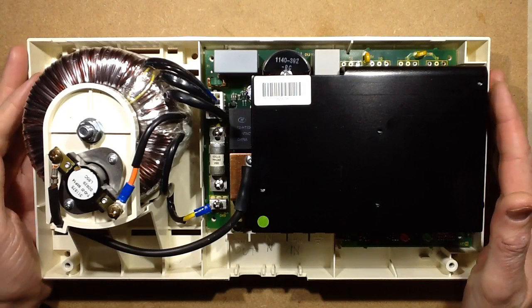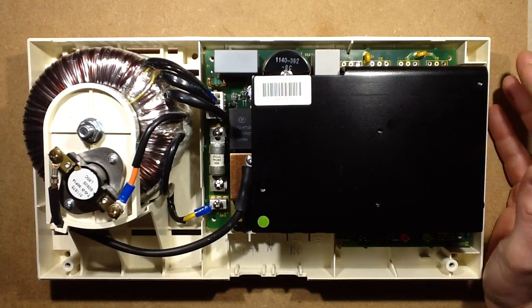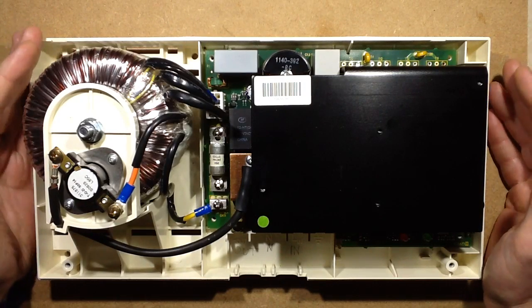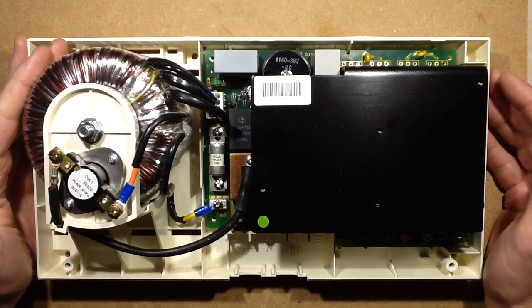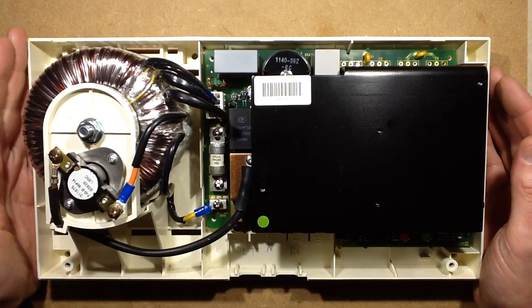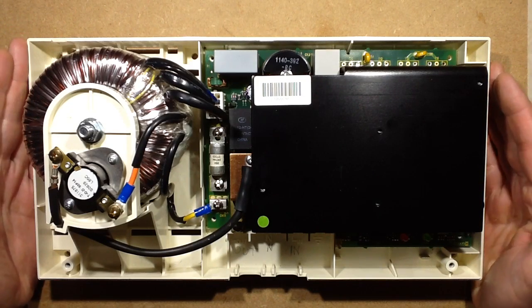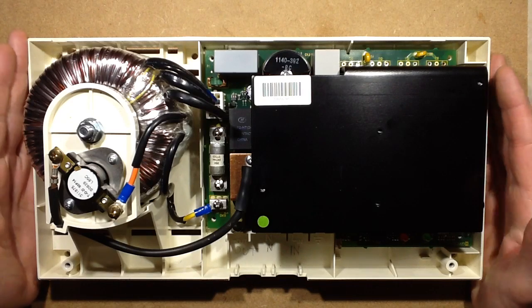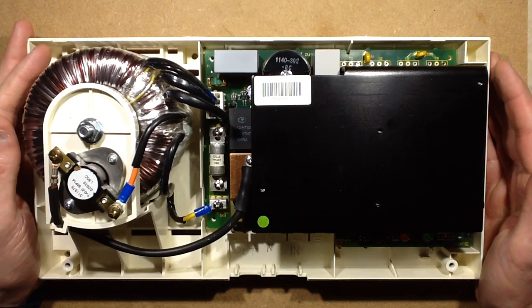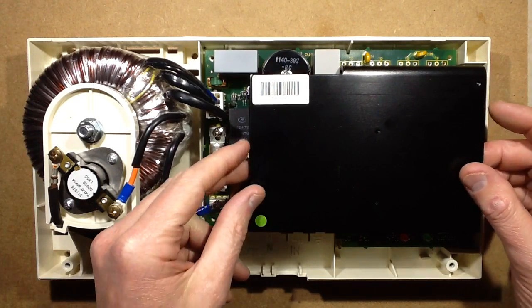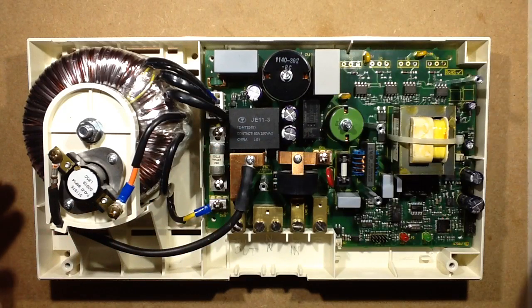This is a rather interesting unit. It was sent to me to do a sort of autopsy on as to why it had failed, because it was blowing fuses all the time. It's a V-Phase VX1 energy saving device, and it basically goes in at your distribution board and it lowers the voltage to your house. And it starts off being quite simple.